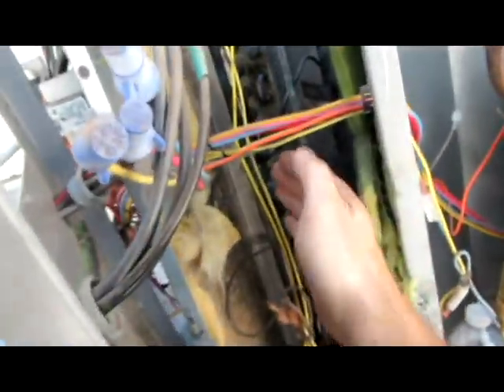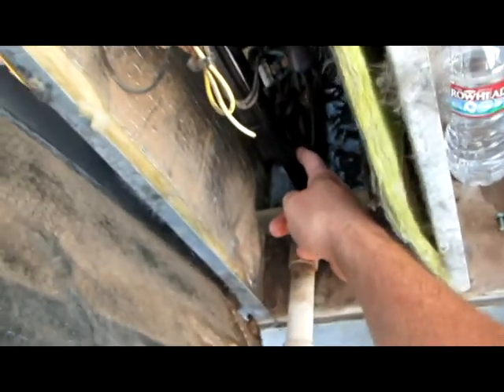Sadly, they're leaking all the way down. I'm gonna have to reach in here with my torches and braze all these fittings — it's leaking here, here, here, here, here, here, here. I got one over here and one over there. They want to try to salvage it, so luckily I am the best brazer in the world — no, not really.